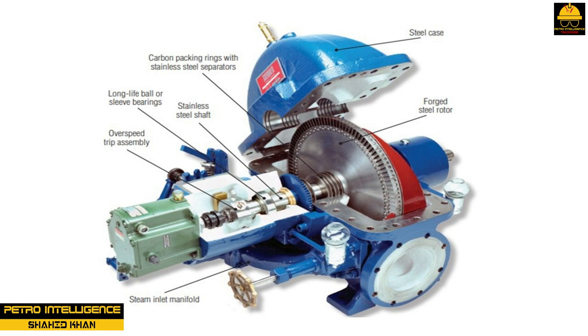Steam turbines are typically classified as condensing, non-condensing, reaction, or impulse. In condensing turbines, exhaust steam flows to surface condensers; condensing turbines operate at vacuum pressure. In non-condensing turbines, exhaust steam is utilized in low pressure steam applications. In reaction turbines, steam is discharged from a nozzle mounted on the rotor; movement is a reactive response to the release of steam from an internal source. In impulse turbines, steam from an external source acts on the rotor to create movement — most plants use this design. Each of these designs can have one or more stages.